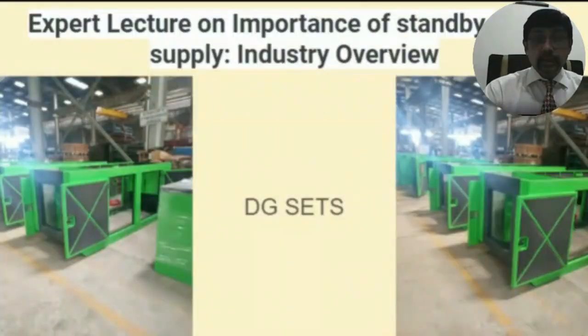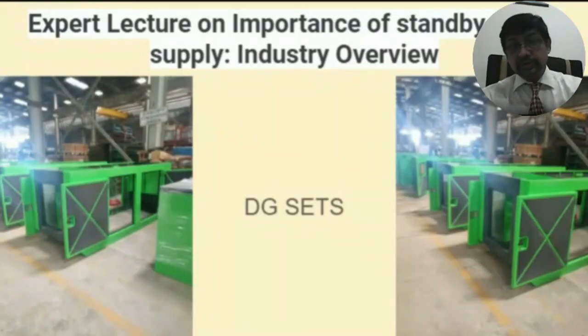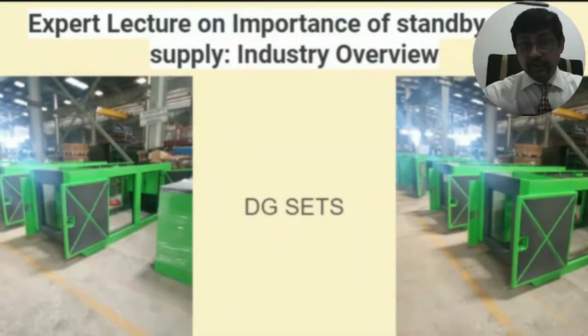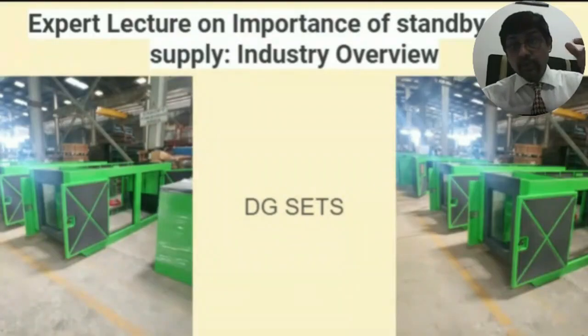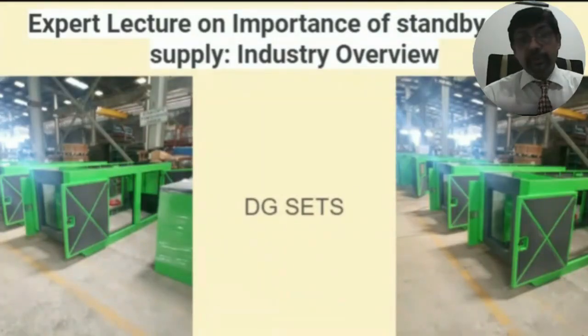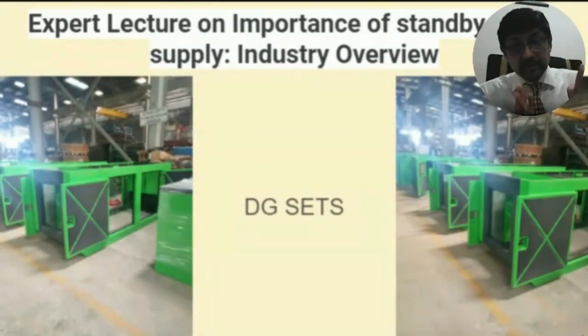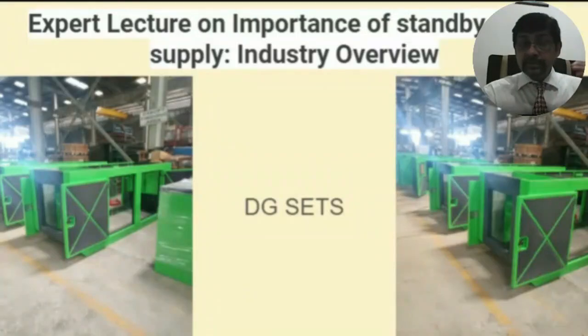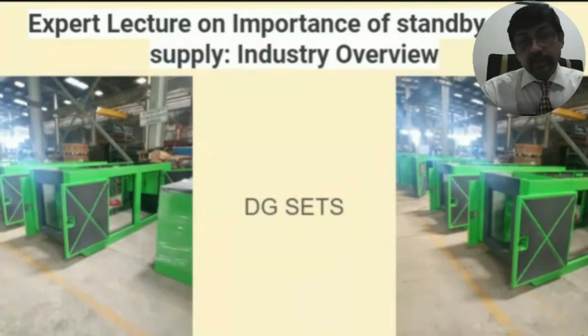Yeah, next. Now, these are the generators where we can see the acoustic enclosures, which are the doors treated with acoustics. The black color there is the acoustics on the doors of the generators. These acoustics are basically 50 mm to 75 mm in thickness. The wall size or the door thickness is 50 mm to 75 mm. And of course, for the big generators, that is 250, 300 kVA and upwards, right up to 750, it is about 4 inches, that is 100 mm. So this is the acoustics thickness, which ensures the noise level is not going above 75 decibels. And these are all designed by the engine manufacturers, and they dictate or inform what kind of thickness is required for the noise.